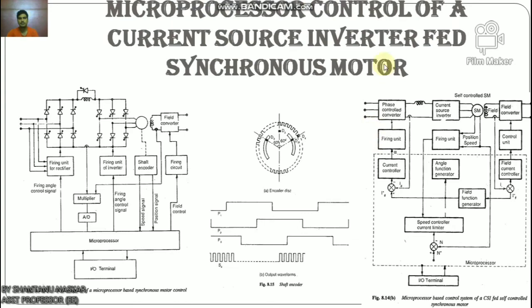Now let us discuss microprocessor control of a current source inverter fed synchronous motor. A drive system employing a current source inverter with synchronous motor has the following features: (1) four-quadrant drive can be accomplished very easily; (2) self-control which synchronizes the gating pulses of the inverter with rotor position provides improved steady-state and dynamic performance; (3) natural commutation using machine voltage is possible in a speed range from 10% of base speed upwards; at starting and low speed, force commutation is required, provided by additional commutation circuits or by interrupting the DC link current. A typical block diagram implementation of a microprocessor for control of a current source inverter fed synchronous motor is shown.